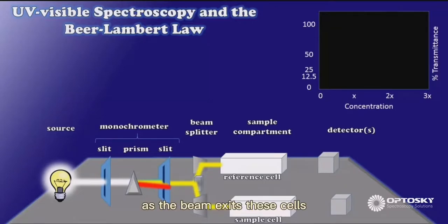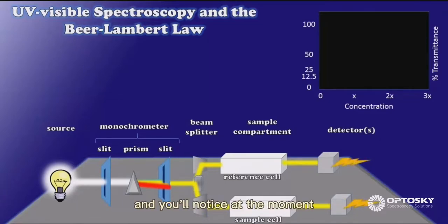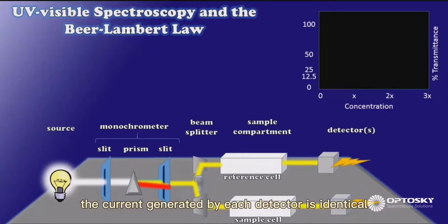As the beam exits these cells, it strikes the detectors, which are firing away, creating an electrical current. And you'll notice at the moment that the intensity of the light exiting both the reference and sample cells is identical. Therefore, the current generated by each detector is identical.